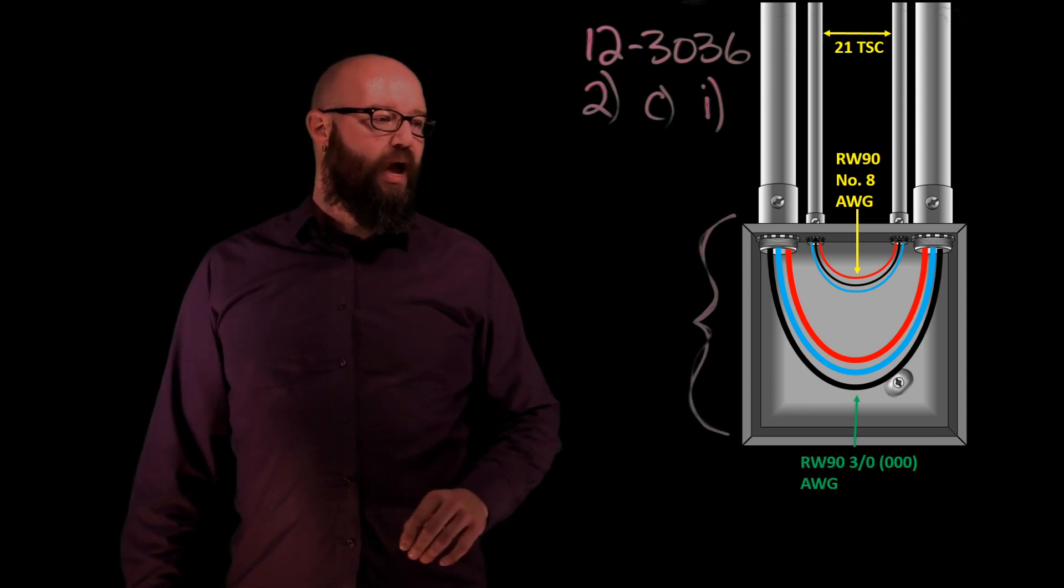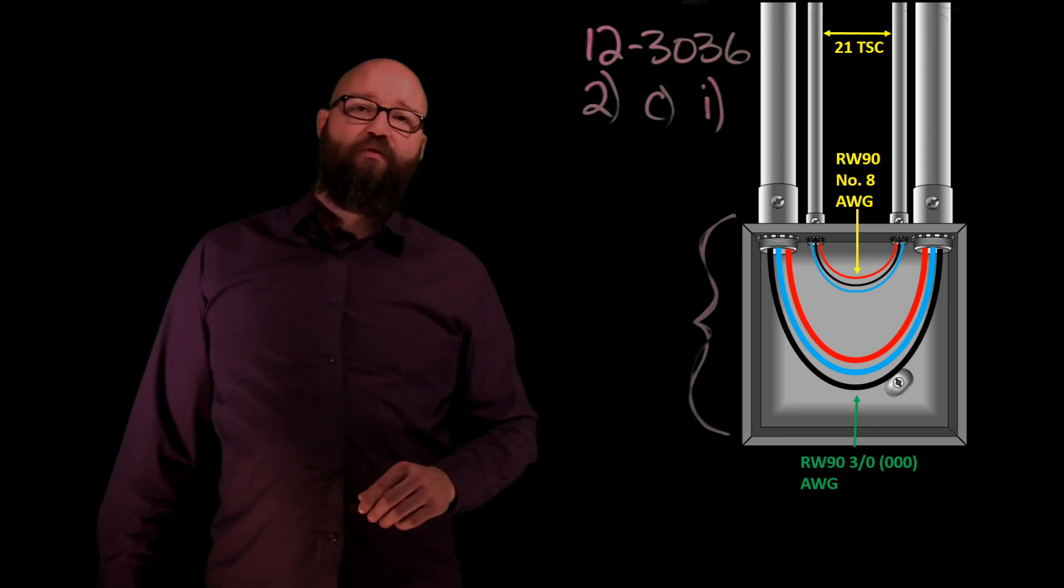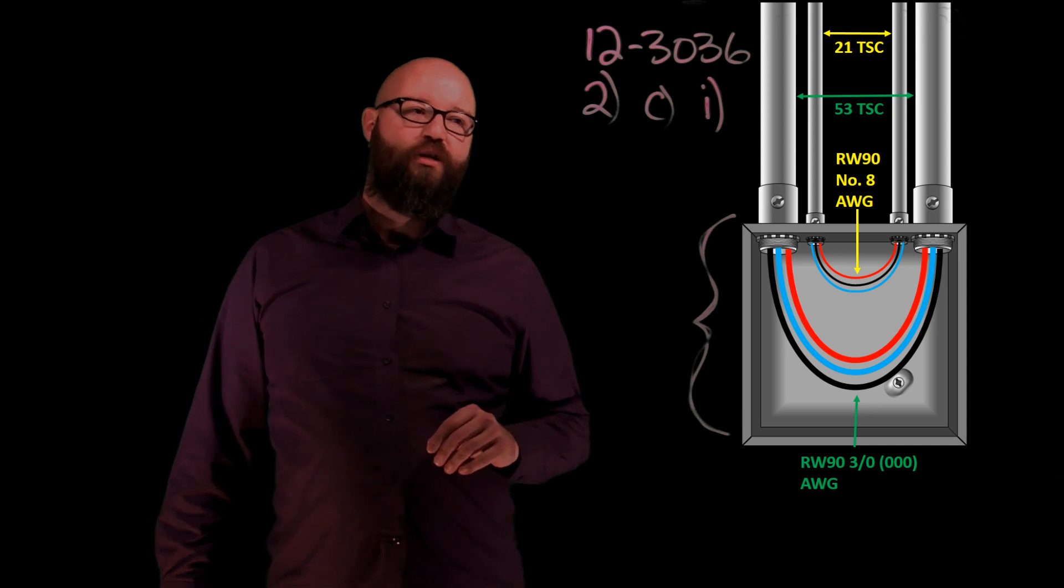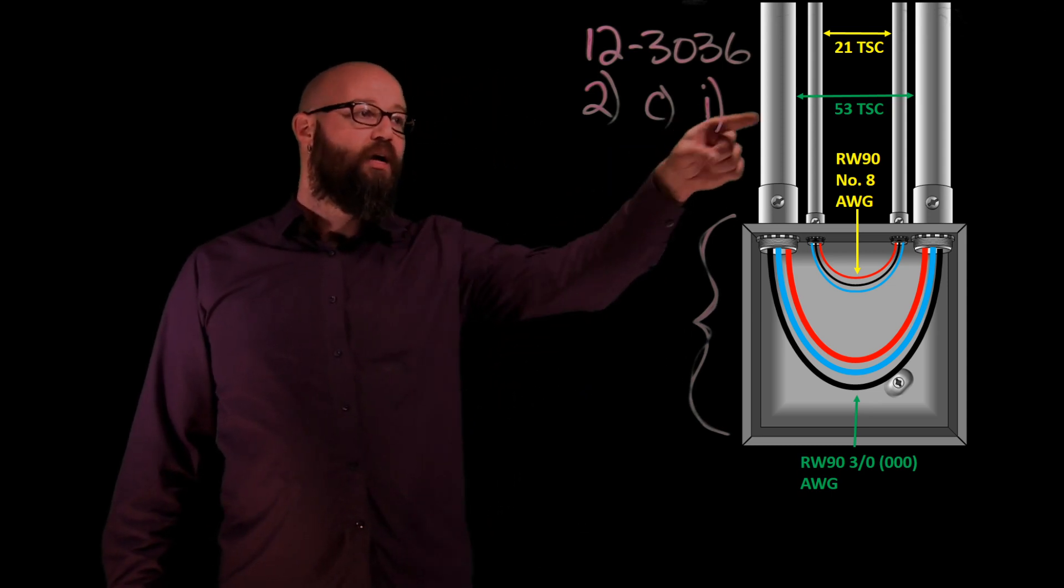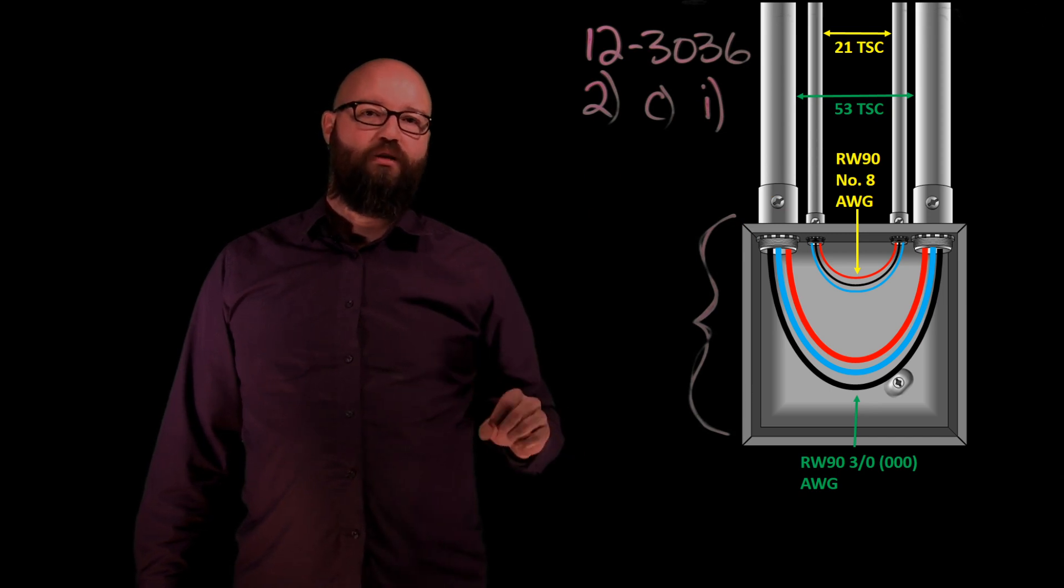What we're concerned with is these larger conductors here. So in these larger conductors we have three of these three ought AWG conductors and if we go to size the conduit again from table six, what we end up with there is a 53 trade size conduit. So my larger conduits are 53 trade size conduit, that's what we're going to start with.